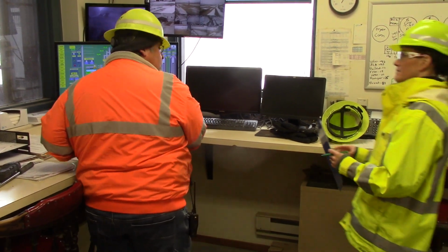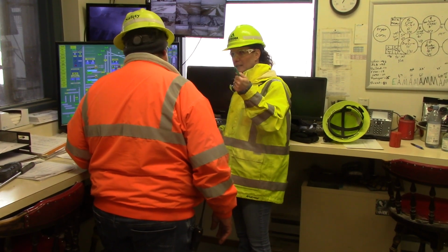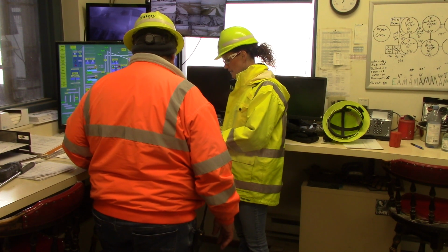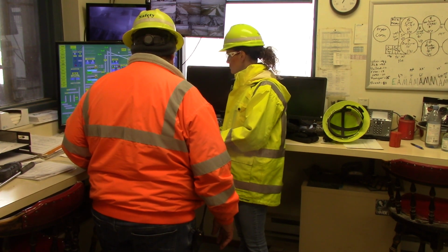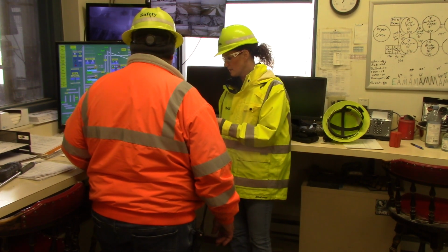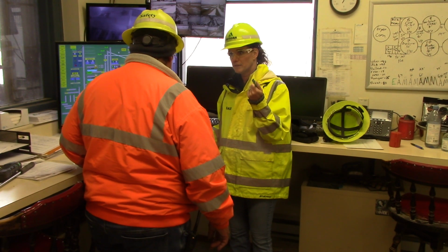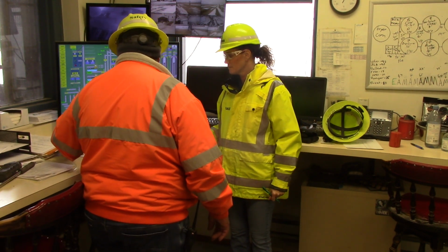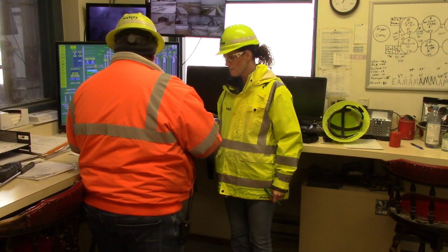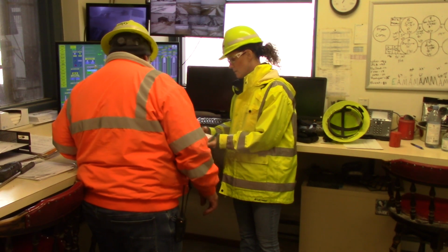Hey Chuck. Beth? So per morning huddle this morning about having to get in and check the sweep in bin 30, I did go ahead, I've got everything locked out and ready to go. And then we did check it on the PLC here to make sure that nothing will run. So I think whenever you're ready, we should be ready to go into bin 30 and get that checked. All right, we'll have to fill out the bin permit, the confined space permit, to begin entry. We'll have to go through this.